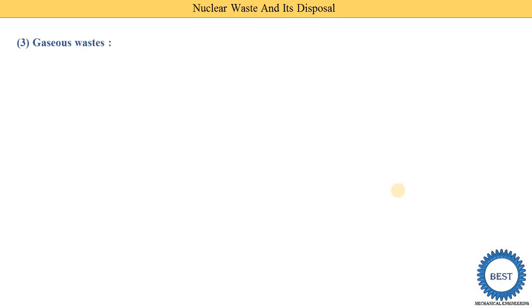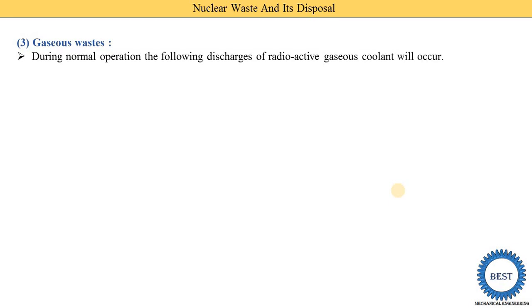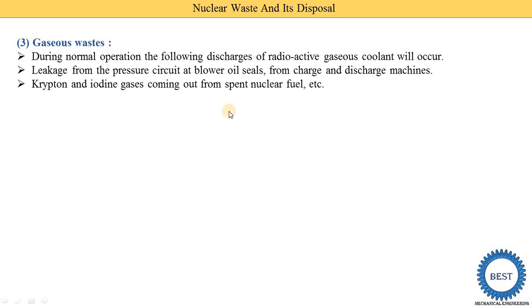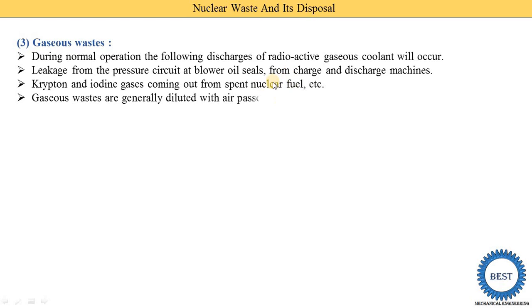The third type is gaseous waste. During normal operation, the following discharge of radioactive gases and coolant occurs: leakage from the pressure circuit at the blower oil seals, from the charge and discharge machines, and krypton and iodine gases coming out from spent nuclear fuels. These gases are radioactive because they originate from the nuclear fuels.